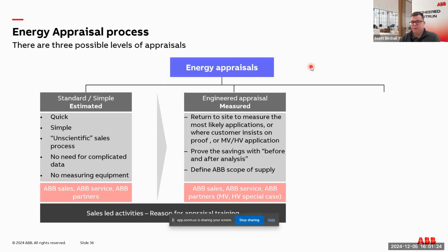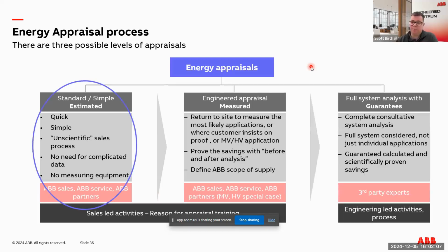Basically, somebody will go to site, measure the application before, then in a lot of cases install a trial or hire drive to measure after reducing the speed of the motor, realizing the savings for the same amount of time, and then compare the two values to see what the savings look like. We've seen people do this with one or two applications first; if they turn out good, they do it with the rest. This is generally done with ABB sales, service, or partners, depending on the site and industry. There are also people in the market who do full system analysis with guarantees.